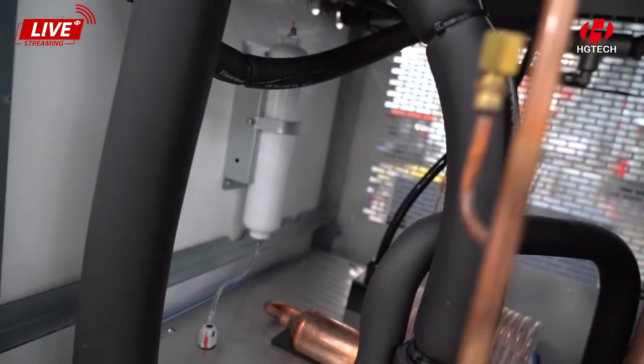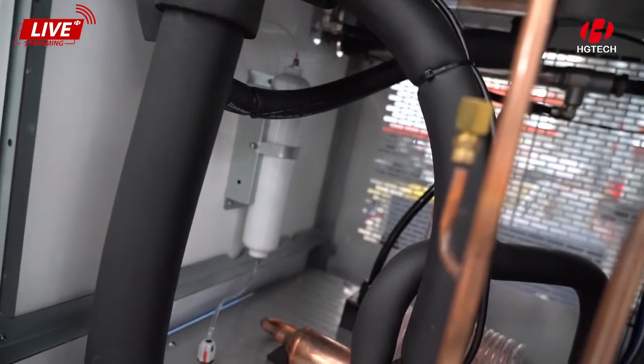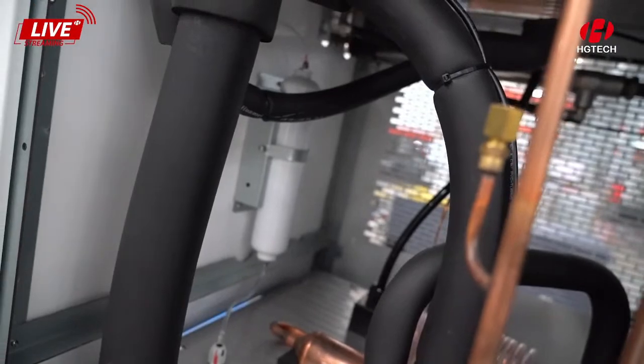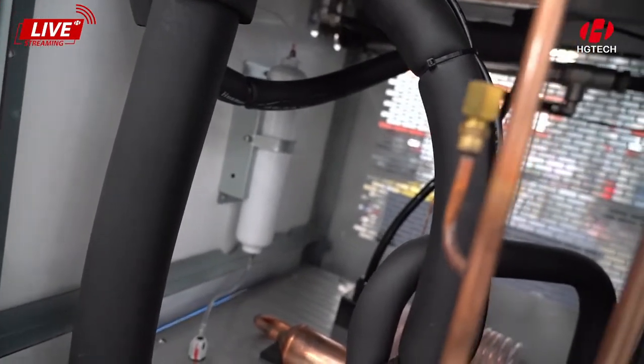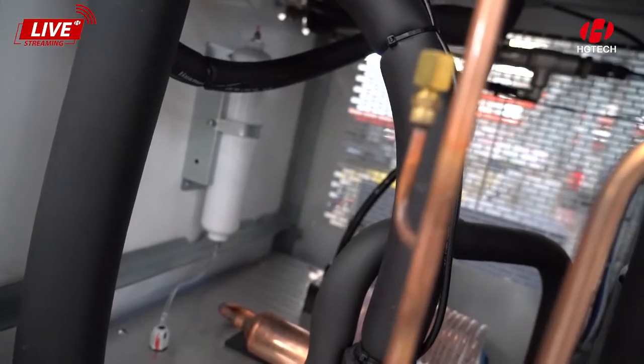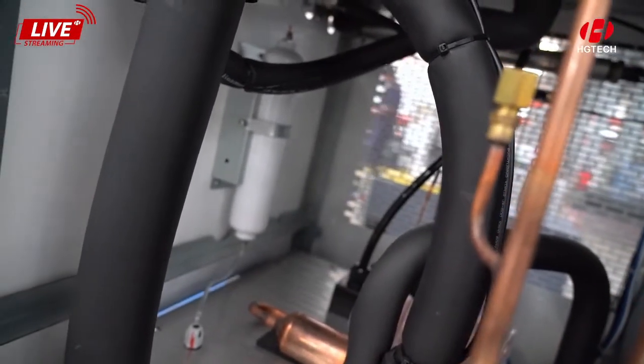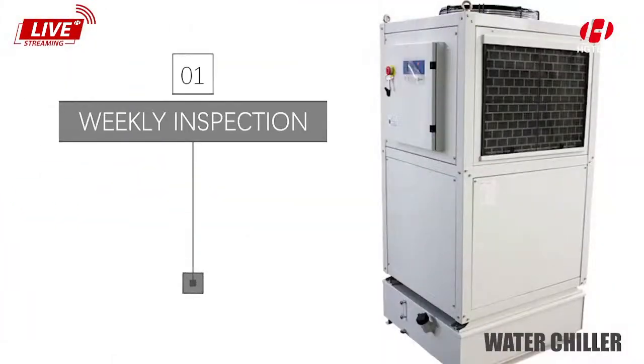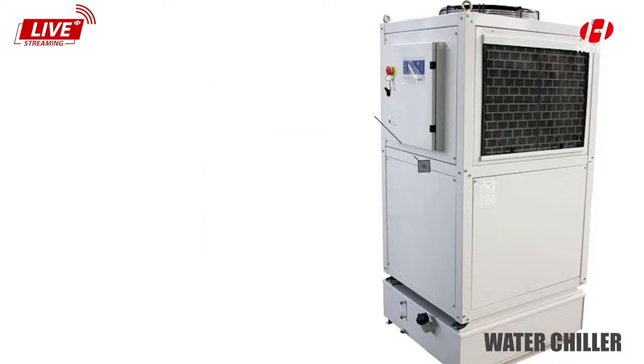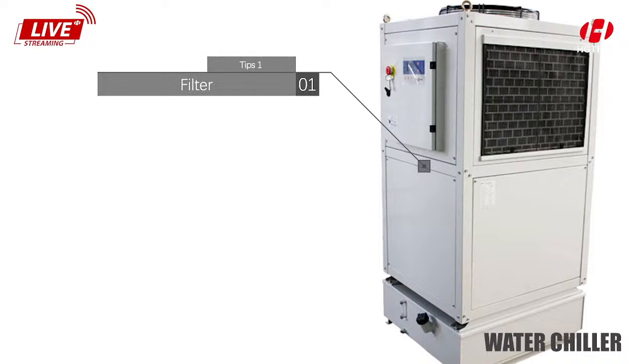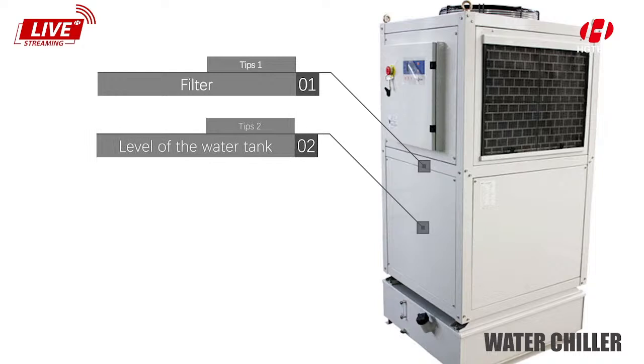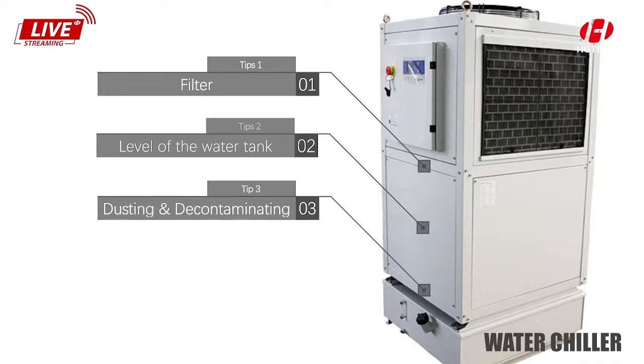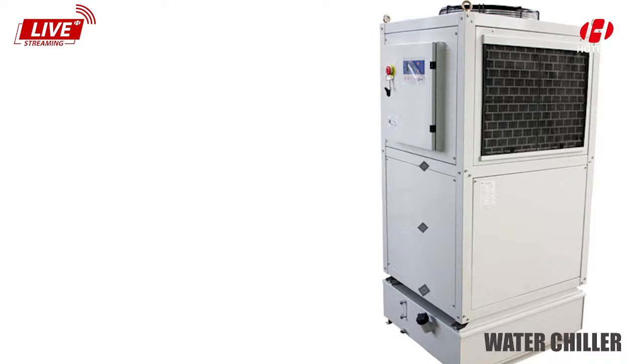It has to be mentioned that the water temperature in summer and in winter is different, so we have to take care if the water will be freezing in the winter, and we have to add some anti-freezing material into the water. Water chiller weekly inspection. The weekly inspection is a major part of the daily maintenance of the chiller. Check the filters and clean the dust and other objects. Check the level of the water tank and fill it when it is low. Dusting and decontaminating the outside of the unit.